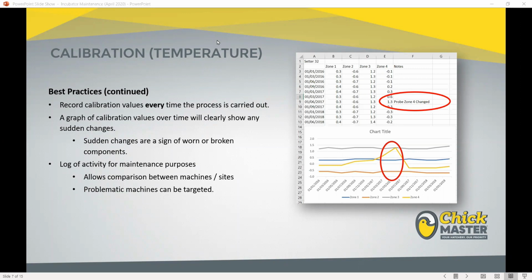The reason being, when hardware starts to fail, when electrical components start to fail, what you'll generally see is an exponential increase in the deviation for that sensor. That's signified by the yellow line on the graph on the right-hand side of this slide, where you can see consistently the reading for the yellow probe was around -0.1 Celsius. And then gradually that's increased up to 0.3, 0.6, and then eventually 1.3. So those figures will get greater and greater and greater. Now, eventually our control will automatically flag that up for you as a probe failure on the machine.